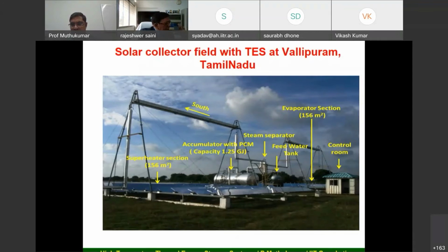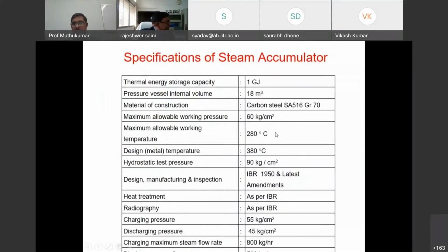This is the specification of the steam accumulator. The designed capacity was 1 gigajoule, the vessel volume is about 18 meter cube, and the design pressure is about 60 bar, but tested up to about 90 bar, hydrostatic test pressure, everything designed as per the Indian boiler regulation. The charging pressure is about 45 bar, or rather 55 bar, and discharging pressure is 45 bar, and heat is stored at about 220 degrees Celsius.